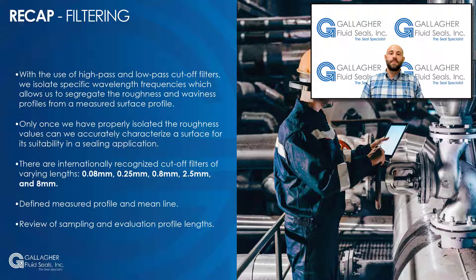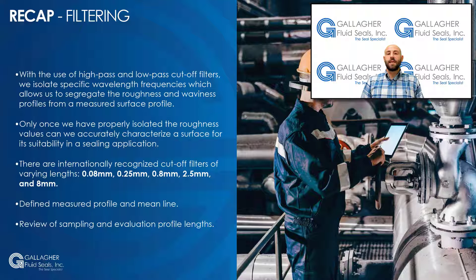To summarize, with the use of high-pass and low-pass cutoff filters, we isolate specific wavelength frequencies, which allows us to segregate the roughness and waviness profiles from a measured surface profile. Only once we have properly isolated the roughness values can we accurately characterize a surface for its suitability in a sealing application. There are internationally recognized cutoff filters of varying lengths: 0.08 mm, 0.25 mm, 0.8 mm, 2.5 mm, and 8 mm. We then defined the measured profile and mean line, as well as highlighted the filtering differences between the primary profile and roughness profile.